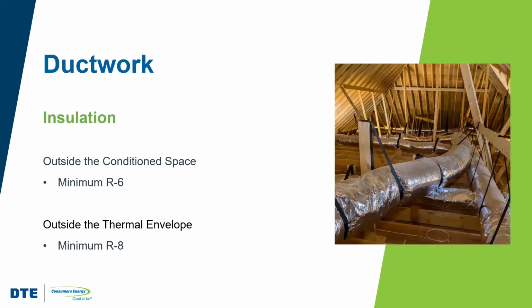Now let's take a look at the HVAC system components. When ductwork in particular is installed in the building but outside the conditioned space, ductwork in a good design will be insulated to at least R6. If the ductwork is not just outside the conditioned space, but also outside the thermal envelope, it'll need to have a higher R value of at least R8, which provides about 33% more thermal resistance.